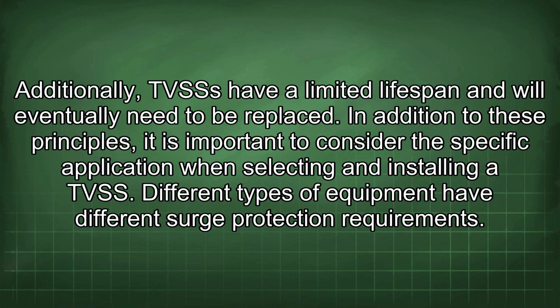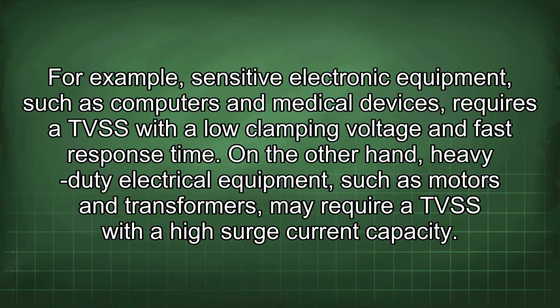In addition to these principles, it is important to consider the specific application when selecting and installing a TVSS. Different types of equipment have different surge protection requirements. For example, sensitive electronic equipment, such as computers and medical devices, requires a TVSS with a low clamping voltage and fast response time. On the other hand, heavy-duty electrical equipment, such as motors and transformers, may require a TVSS with a high surge current capacity.